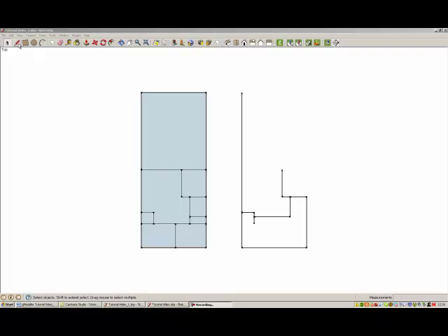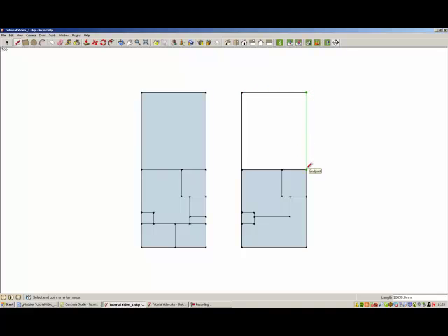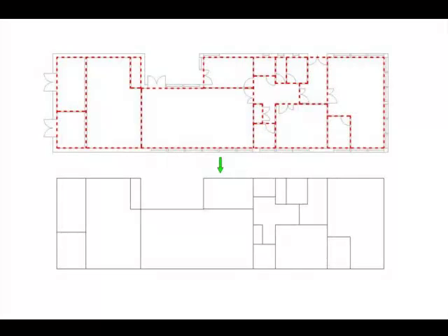The first task is to generate the floor plans of your building. This can be done by importing a DWG or DXF file from AutoCAD, or you can simply draw floor plans within SketchUp using the line tool. We use the internal line of external walls and the center line of all internal walls to ensure that the overall floor area we are modelling is correct in the building model.